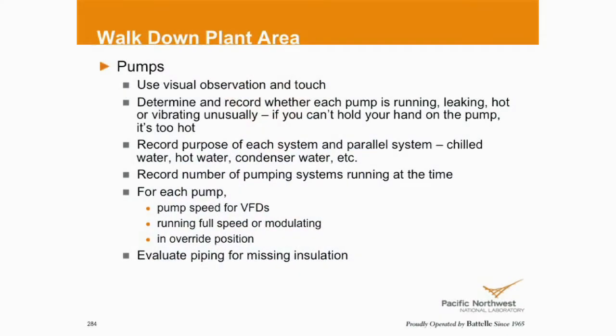And we see more and more people doing this on 100% outside air. We talked about labs. Somebody said, I've got a vivarium and I've got biological labs, 100% outside air. What we're moving to on our labs is we've got 4 fans or 3 fans that move supply air or exhaust. We're running all of them. They're VFD driven, and the sum total of each individual fan with VFD is less than if I ran 1 or 2. Great opportunity.